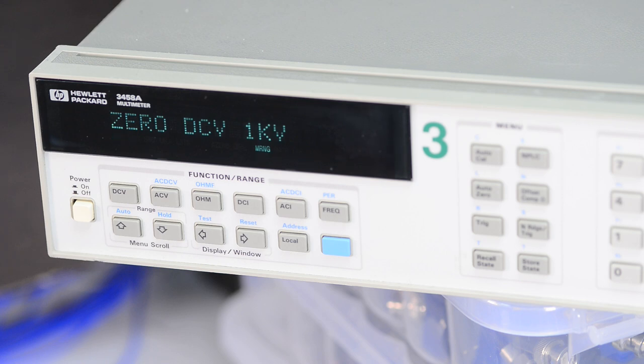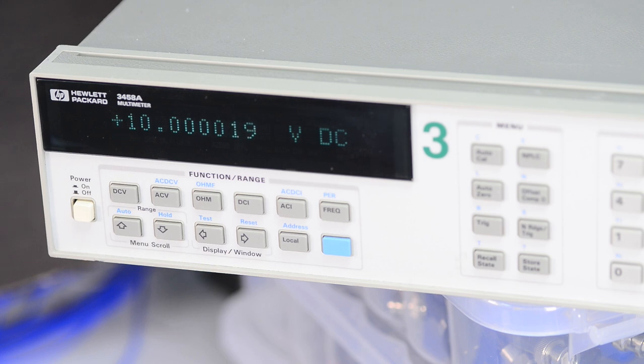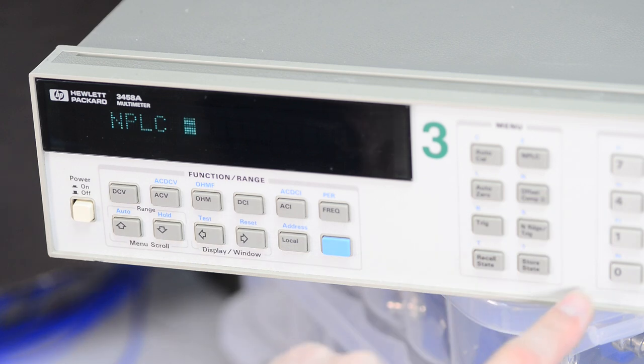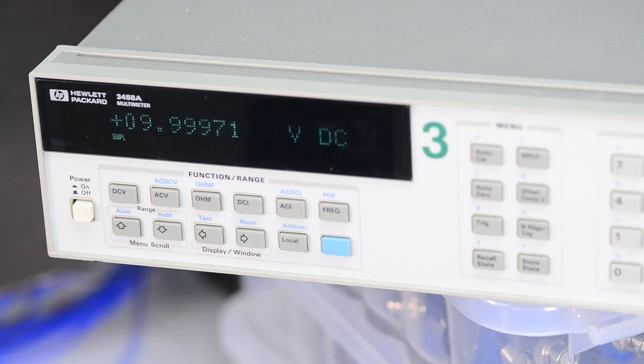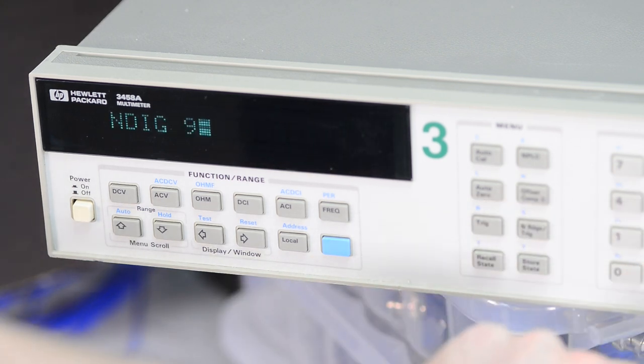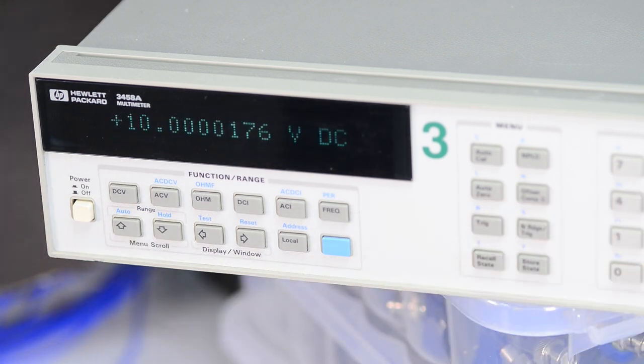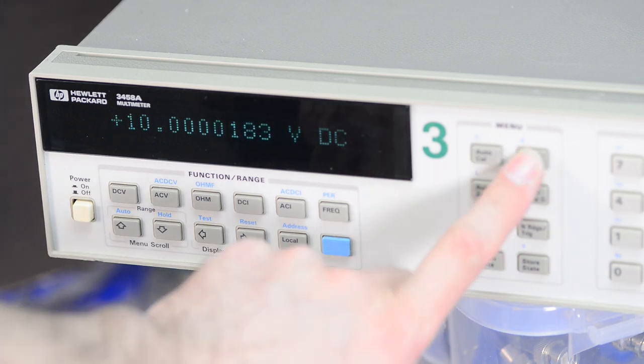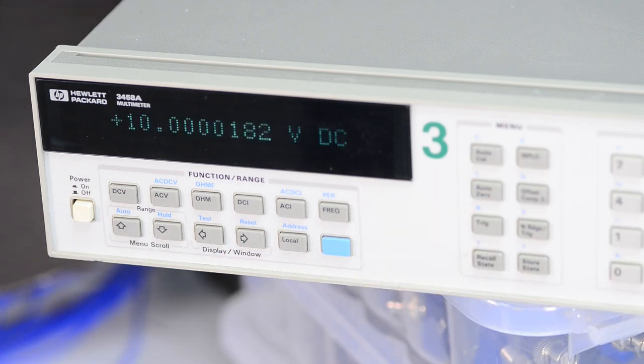So it takes about 150 seconds. And here we have almost exactly 10 volts. It's pretty close to what's expected, given that we have an unknown A3 installed with a supposedly still drifty but baked U180 assembly. So let's test different NPLCs. Fast NPLC usually works even on bad boards, but the slower NPLCs, like NPLC 10 and slower, are more difficult for a bad A3 board to run and often cause more frequent errors.